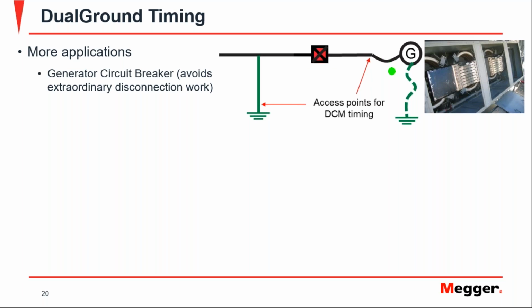And disconnecting this generator is not the most efficient thing, or not the greatest activity you can do. It represents a lot. There are a lot of links there, and you need to connect and torque those. Sometimes getting access to those links is very difficult, and it might represent a day's worth of work.